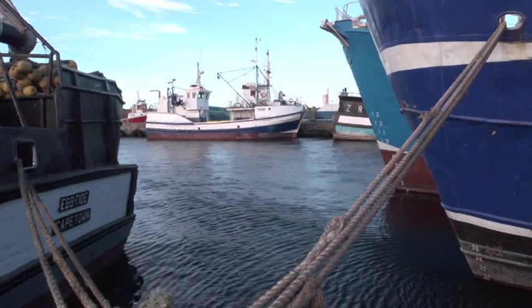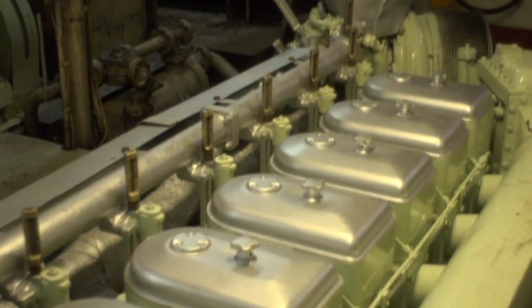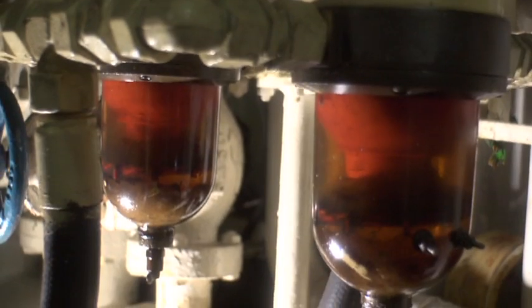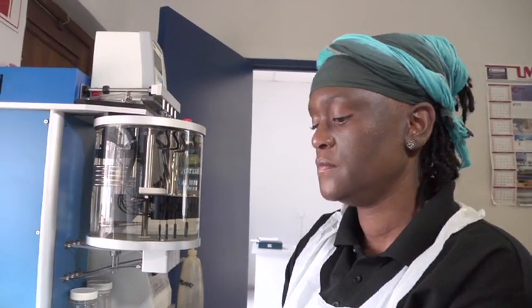Water is the greatest concern because it is the most common form of contaminant. The effects of water in diesel can be serious. Water can cause the tip to blow off an injector or reduce the lubricity of the fuel, which can cause seizure of close tolerance assemblies such as plungers.